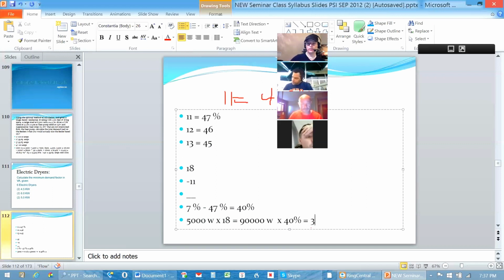So it's 36,000 total kVA. I usually use the calculated demand load as a volt-amp value, or they express it in volt-amps, and the watt value being a connected or nameplate load for appliances. But they're interchangeable. I could call that 36 kW, or I could call it 36 kVA. It would not make any difference at all, according to the actual wording in the article 220.54 or .55. Both tell you that the kVA and the kWs are going to be the equivalent rating according to those sections. So there's no difference. Okay. Any questions on that?